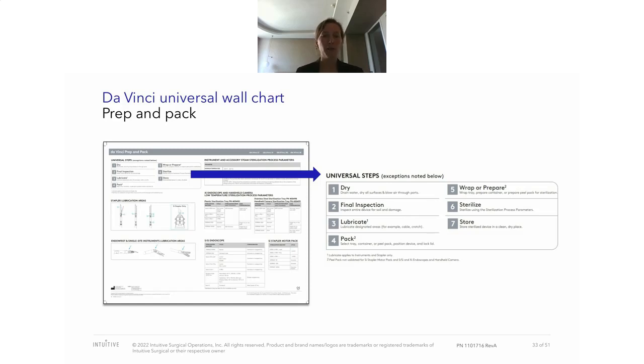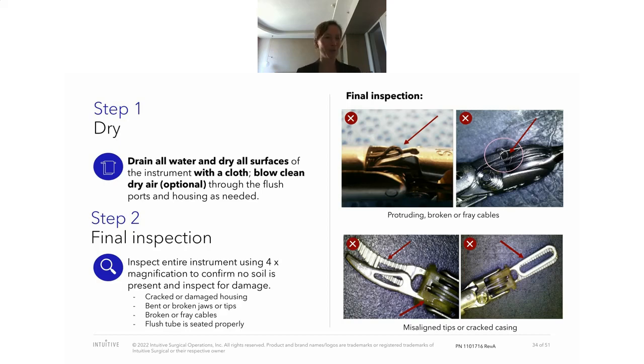But now going to the universal steps for cleaning, you can see drying, final inspection, lubrication, and we'll go through those in a second in more detail. I'm very quick with pressing my next button. So the first step, drying. If the instruments are still wet, it is definitely important to drain all the water, dry the surfaces, and also if need be, or if you have it available, to use clean dry air to ensure that the instruments are dry. And then final inspection.